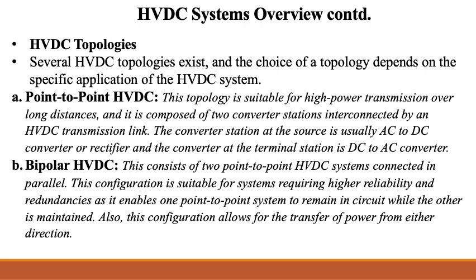The second is bipolar HVDC. This topology consists of two point-to-point HVDC systems connected in parallel. This configuration is suitable for systems requiring higher reliability and redundancy, as it enables one point-to-point system to remain in circuit while the other is maintained. The advantage of bipolar HVDC is that it allows transfer of power in either direction.